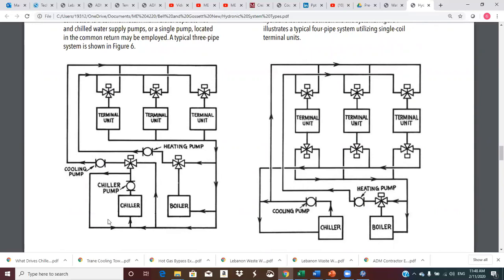But we don't do that, because you might have a unit heating or cooling, and you want to preserve that return water temperature. On the boiler side, you want to keep it as warm as possible, and on the chiller side, you want to keep it as cool as possible. So this you really don't see anymore.